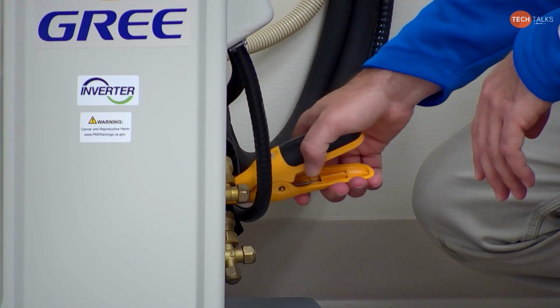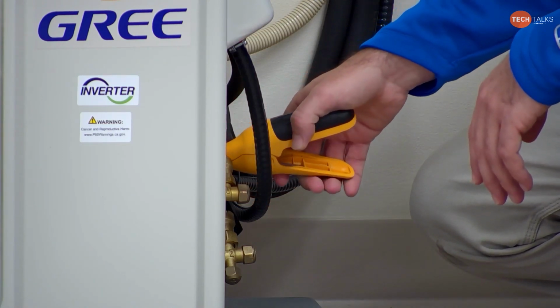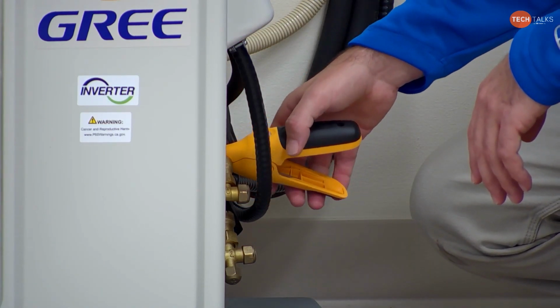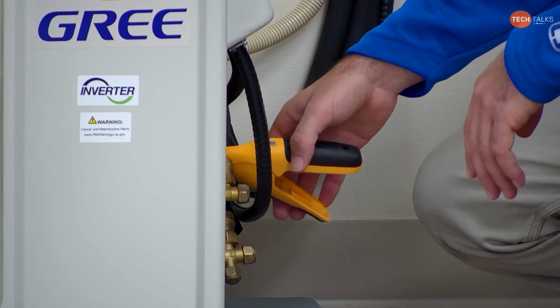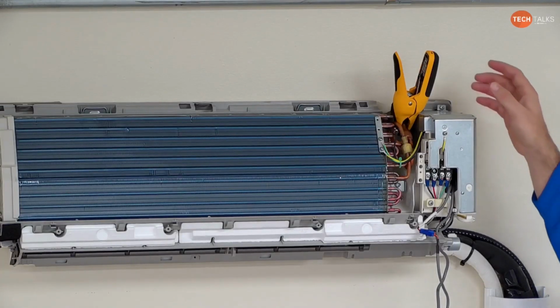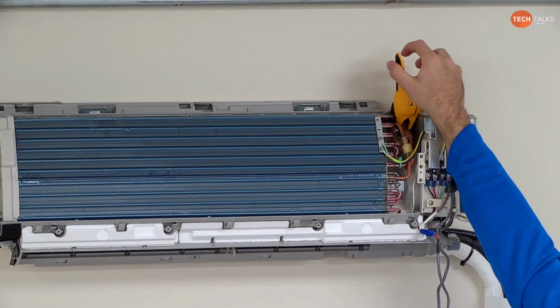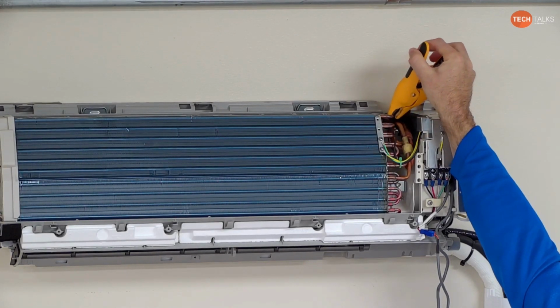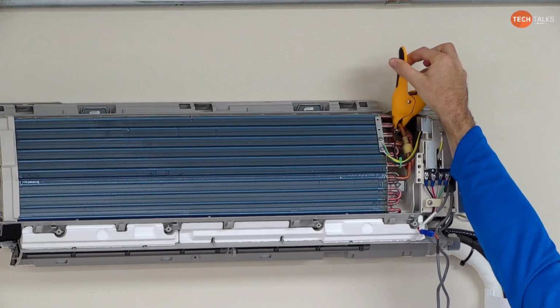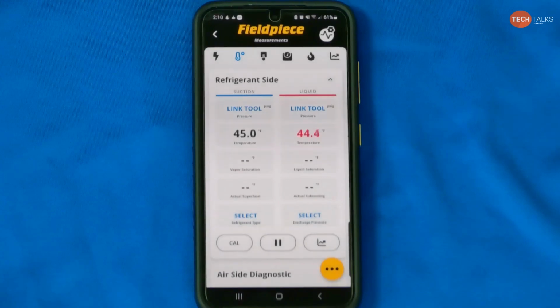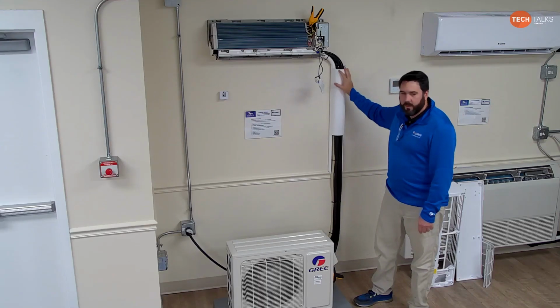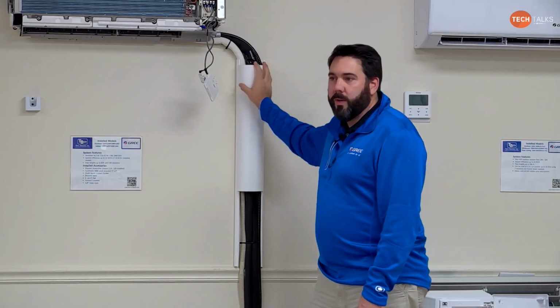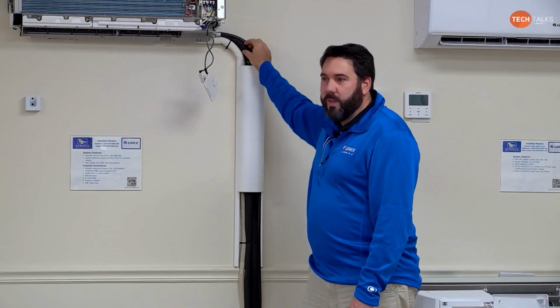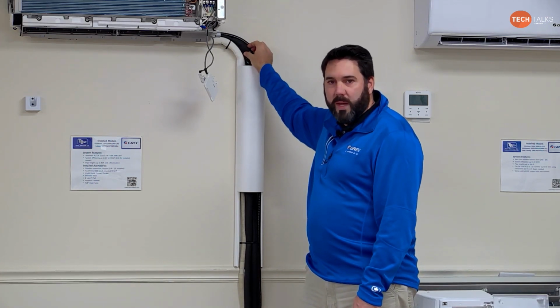So I'm going to go ahead and move to the liquid line with my clamp on the outside unit as close as I can get to the outdoor. And also on the indoor unit, I'm going to move that clamp to the liquid line as well so we can get our reading there. So for this particular system, we know that the line set does not have any restrictions in it. We don't have to take the time taking the line set cover off. We don't have to remove the insulation to physically inspect it.